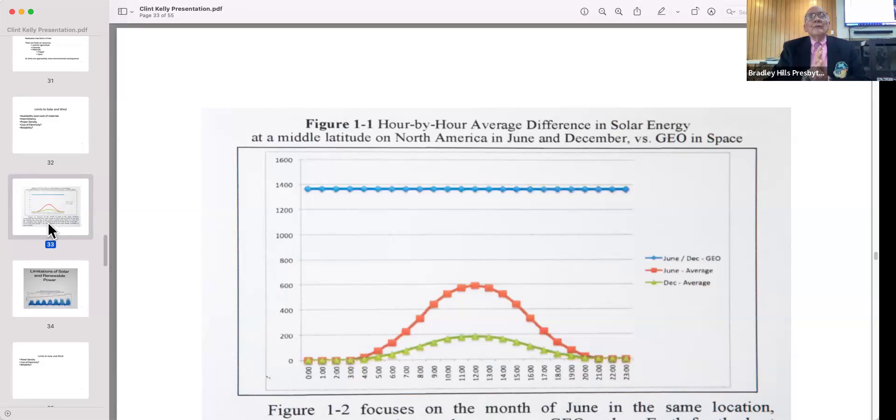The trick is to know that when somebody says we have added so many megawatts or gigawatts of solar power or wind power, it ain't what you think. What they're doing is reading the numbers off the base plate that says under ideal situations, probably never to be experienced, you will get whatever the base plate says. In reality you get maybe 20 or 30 percent of that. What you really get is called the capacity factor—it's what you get over some period of time versus what the nameplate says. It's a percentage of nameplate value.